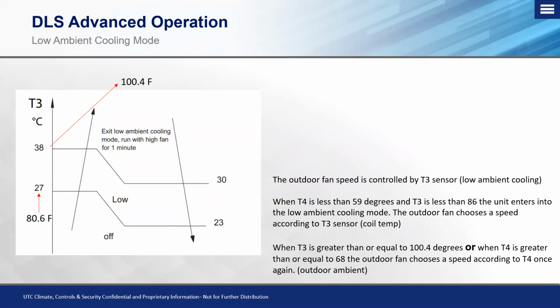So we look at that fan motor in low ambient cooling mode. The outdoor fan speed is now controlled by the T3 sensor, which is the coil temperature sensor, for low ambient cooling. We look at T4 as being the outdoor ambient temperature. So when the outdoor temperature is less than 59 degrees and the T3, which is our outdoor coil, is less than 86, the unit enters into the low ambient cooling mode.